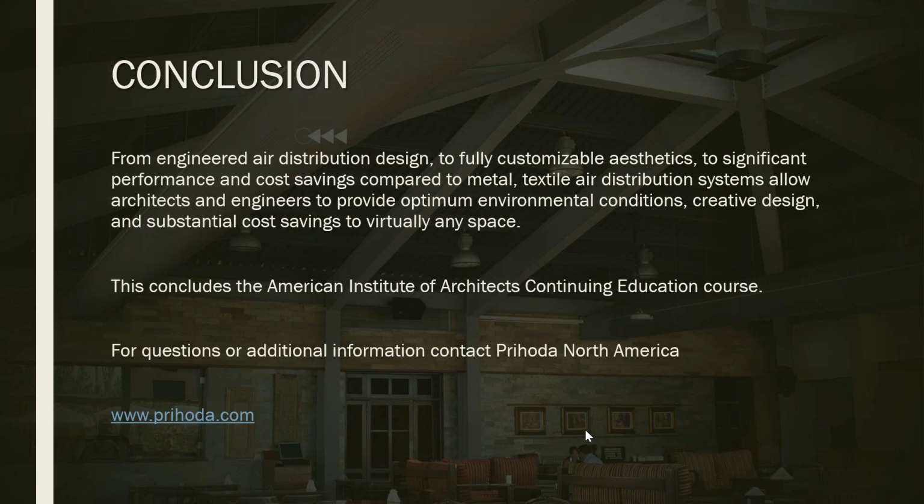The only time that we have ever seen, which is very rare, I haven't seen it, that the suspension would lose its integrity is if it's designed improperly, which never happens because the software will tell us. But let's just say I designed it at a 1/2 inch static pressure, and you have 2.5 inches going through that fabric.